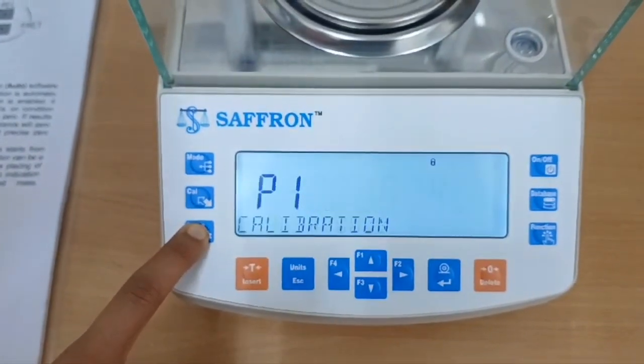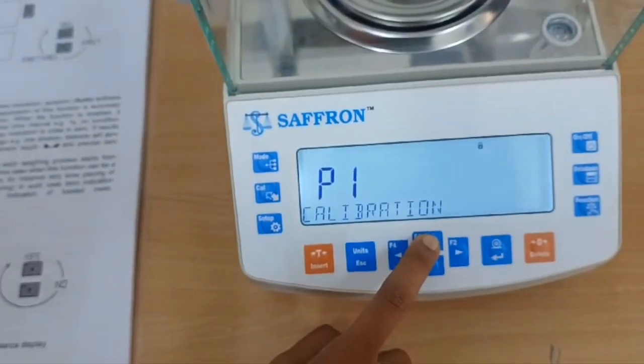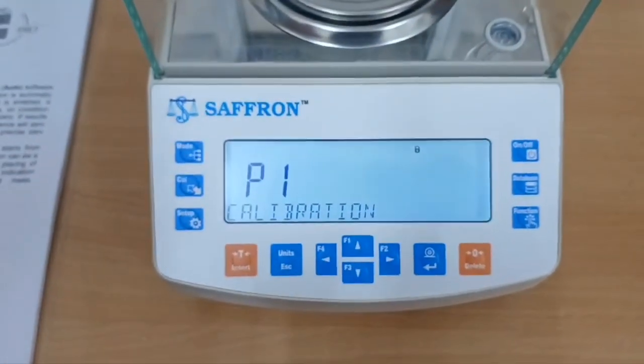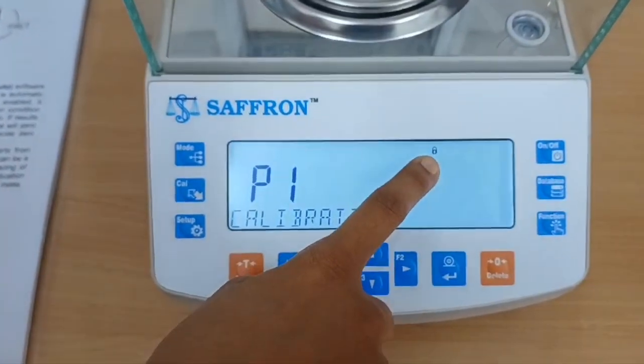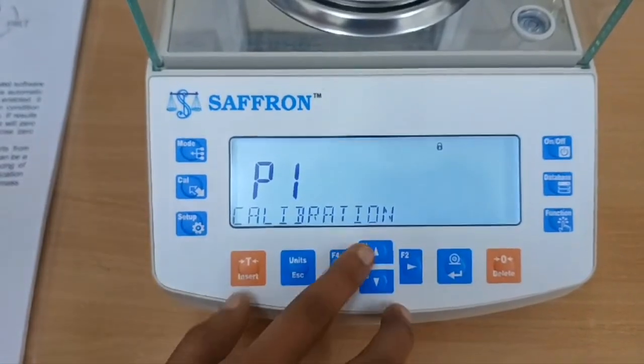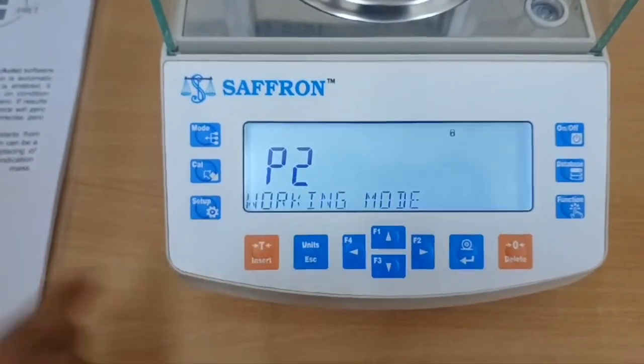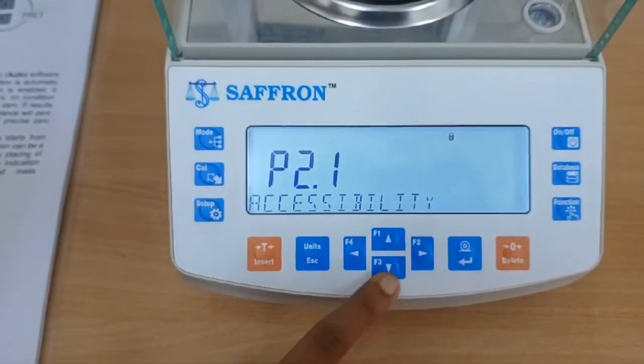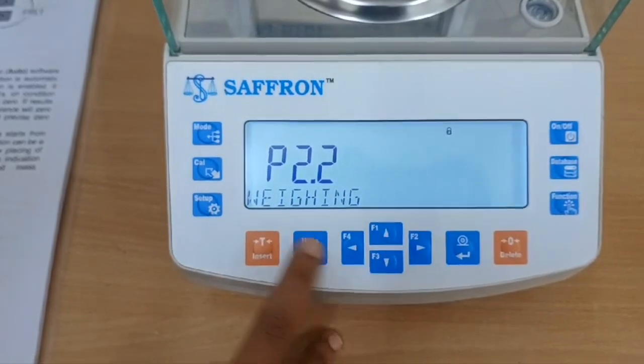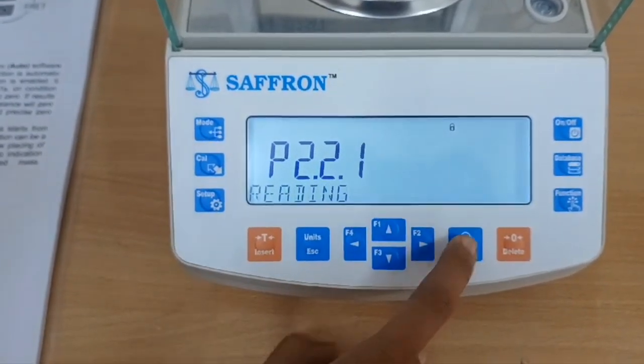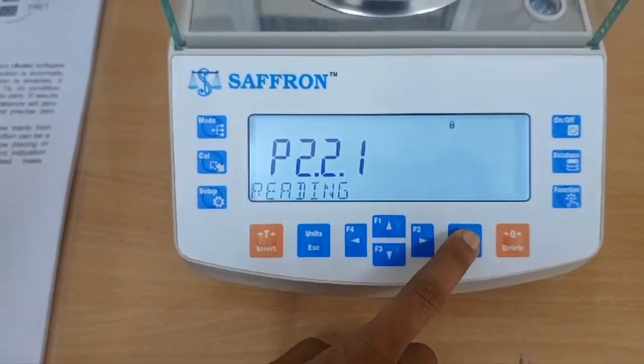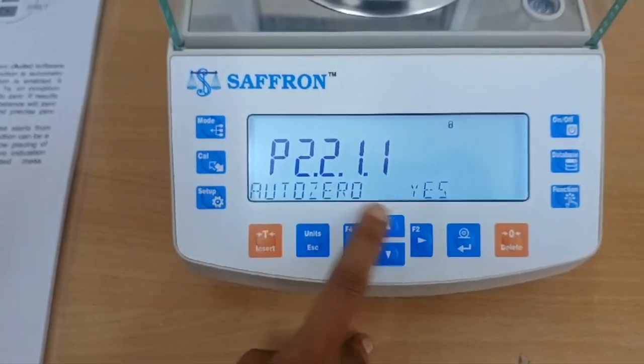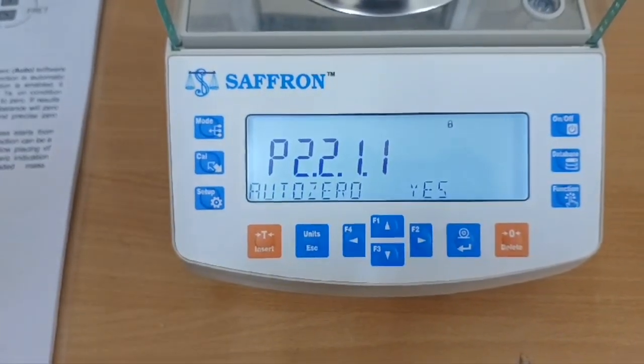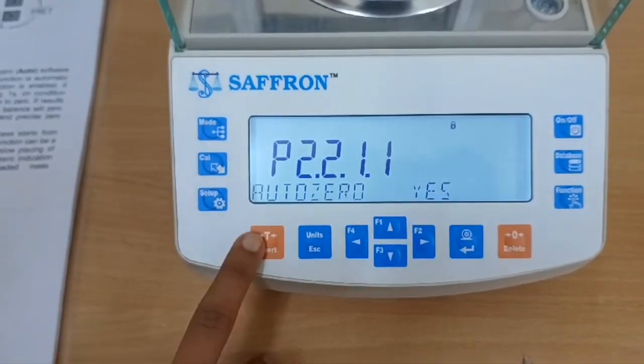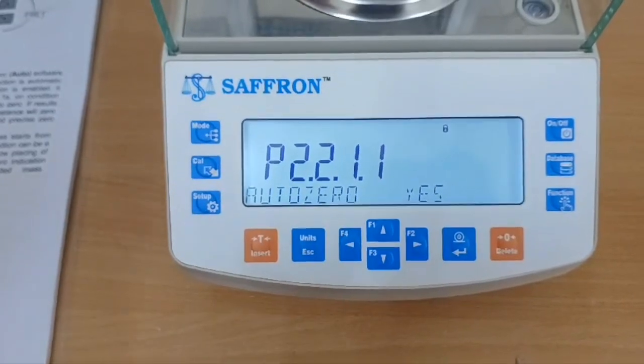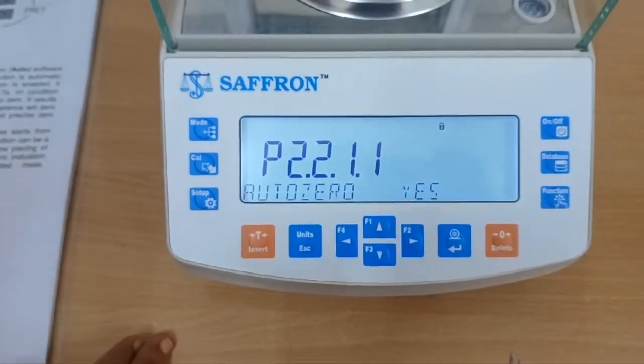So under setup, in order to make any of these changes, you need to be logged in. As you can see, the lock symbol is visible, which means we are logged into admin. So under P2, we go to working mode and click enter. Here it shows accessibility. We need to be in weighing. Click enter. Under the reading, we click enter. As you can see, it says auto zero, yes. That means the auto zero function is currently on. In order to change that, you can click the enter button and it will go back to no. The readings shuttle between yes and no, so clicking enter will only change the reading, switching the function off or on.